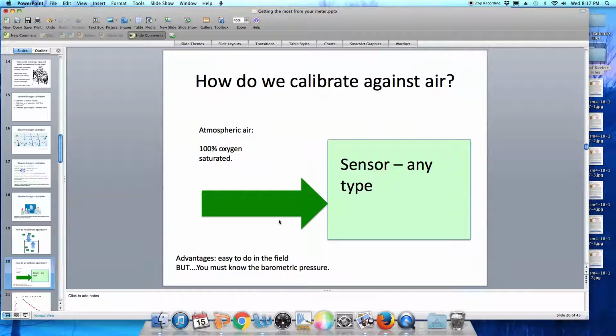If you find your readings seem to be drifting, you can just put your meter back in the calibrate mode and redo the air calibration or the field calibration. The disadvantage of this is that you must know the barometric pressure or your altitude above sea level. You have to know how much air pressure is pushing the oxygen through the membrane so that it can react with your sensor.